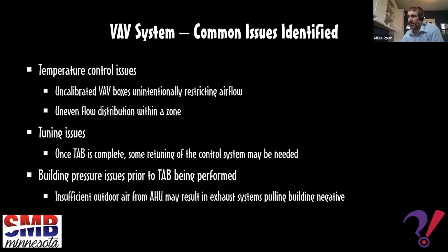Building pressure issues can be a major issue, and those are often realized prior to TAB being brought in. And if you've got a building where TAB was never brought in, you're probably going to have building pressure issues. Going back to that casino project I was talking about, me and Rebecca originally got brought in because they were having two major issues. In the summer, excessive humidity within all of the resort, right? The casino, the attached hotel, common spaces, way too much humidity. Now in the winter, they're also getting very big drafts of cold air coming deep into the space. And they brought us in there to take a look at the ventilation systems to figure out what was the cause of this. And it was actually fairly easy to put our finger on.